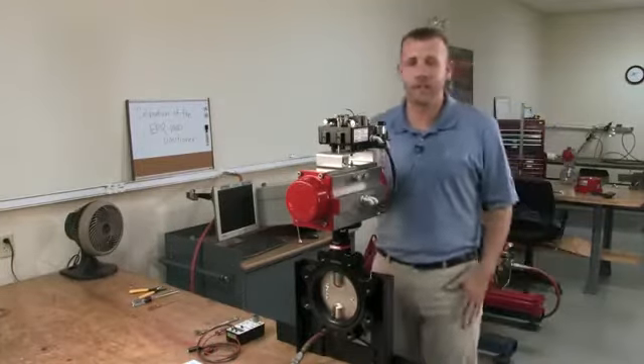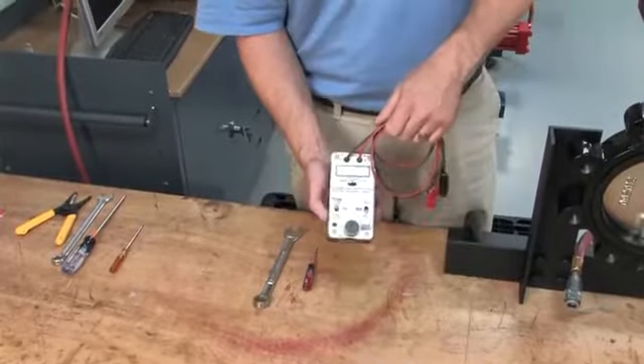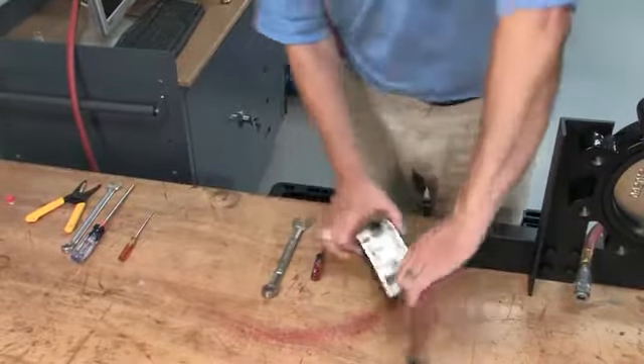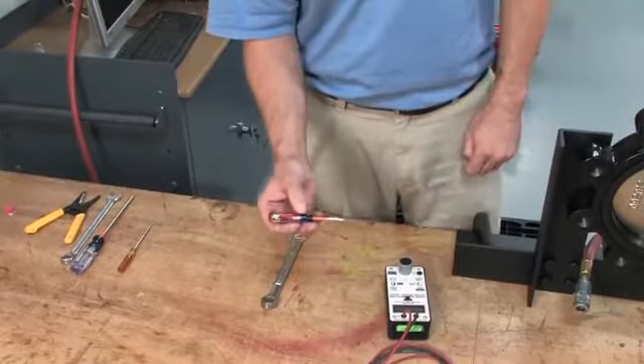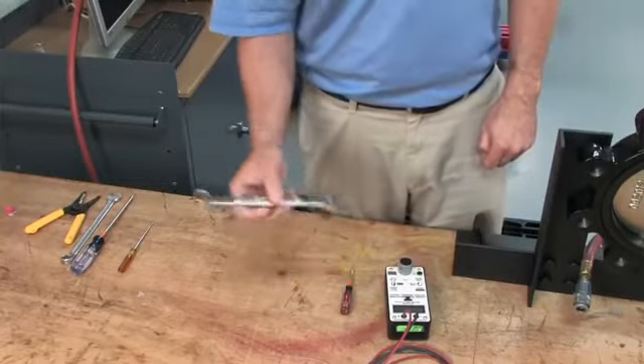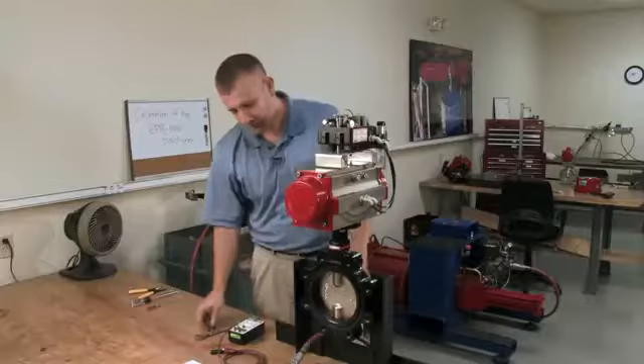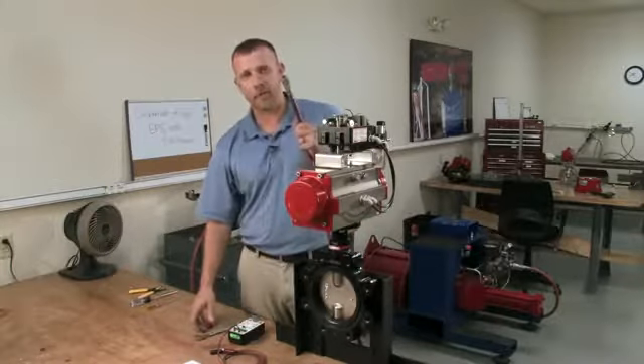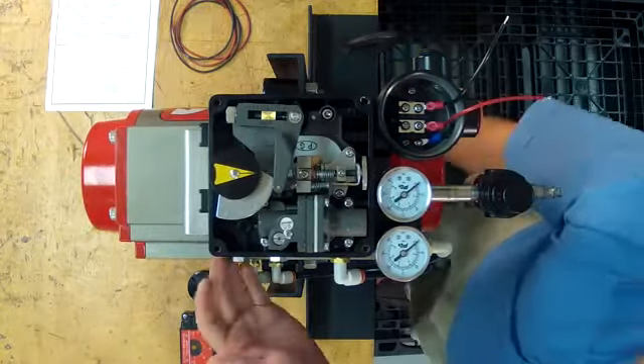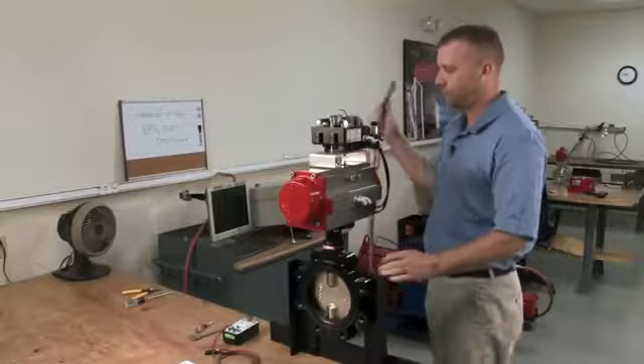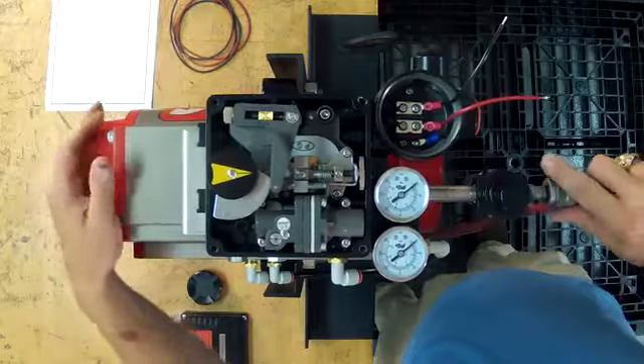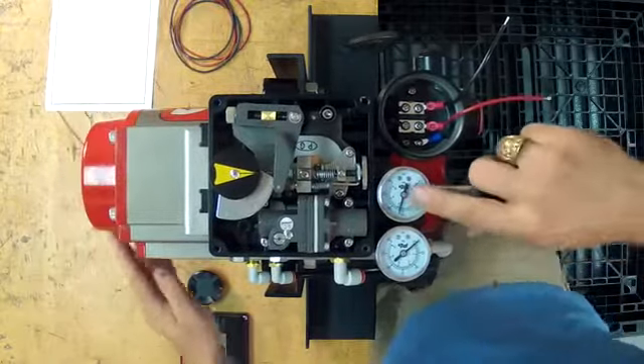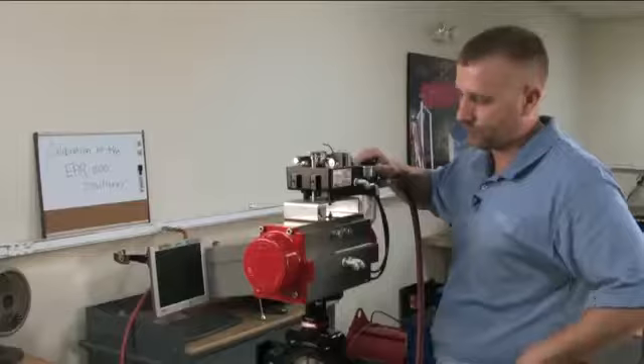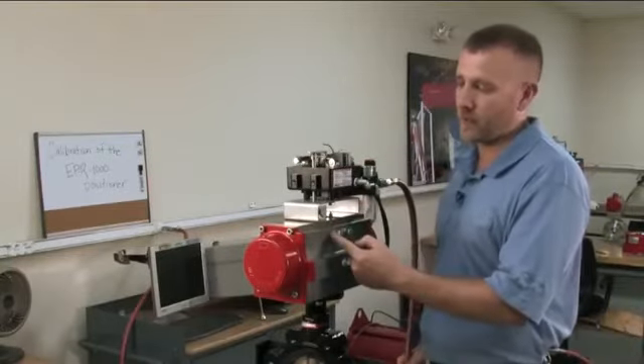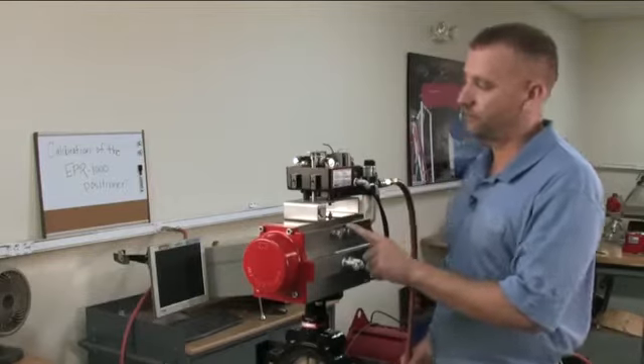A few tools you will need for today's calibration. We have a 4-20 handheld calibrator, a flathead screwdriver, and the 11/16 wrench to adjust our travel stops. Also, clean shop air. Okay, for today's travel stop adjustment, we're going to introduce air on the actuator. This package is sized for an 80 psi air supply, so we need to set our bench regulator to this air supply. This is our counterclockwise stop and our clockwise stop.